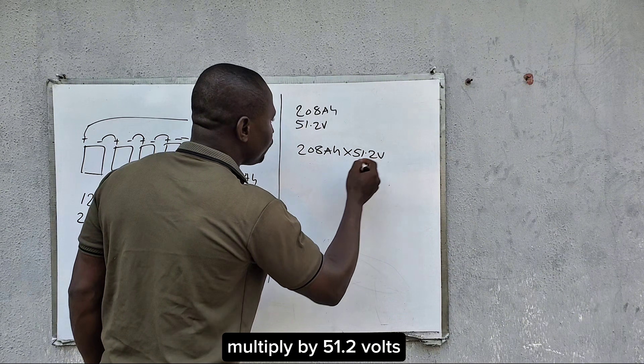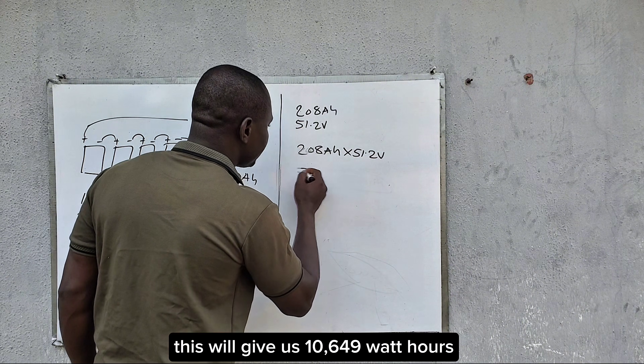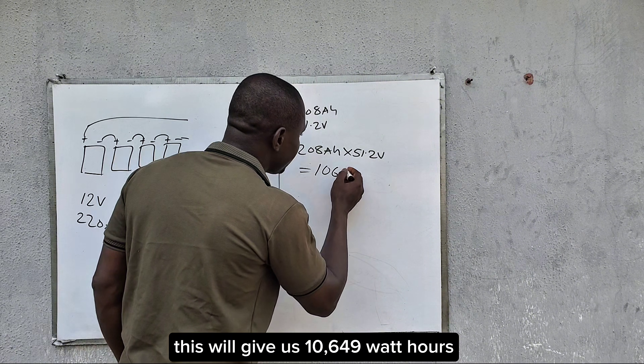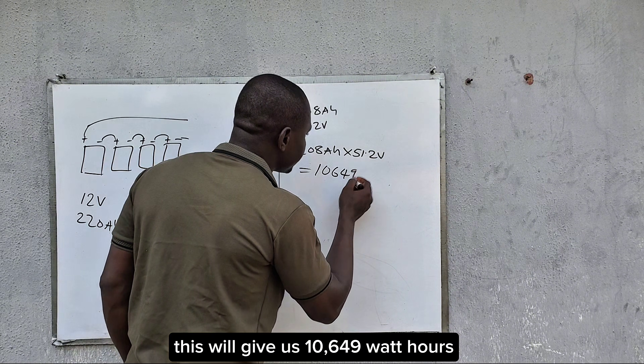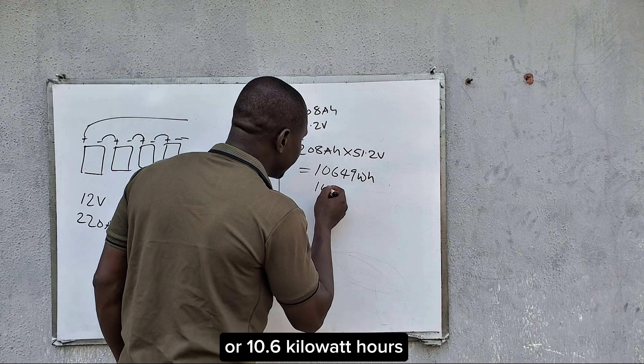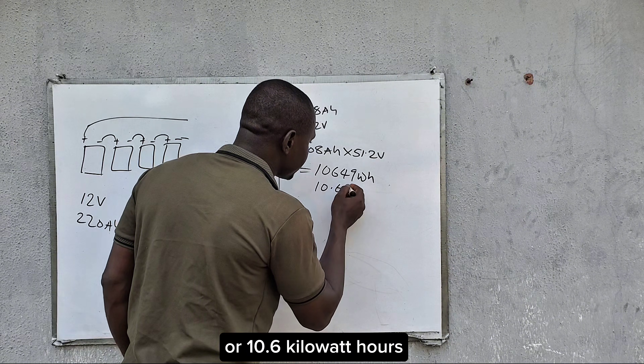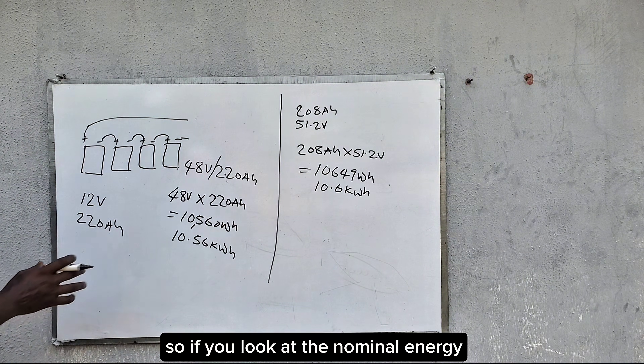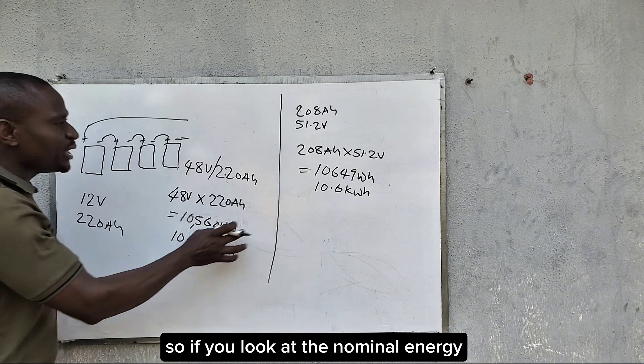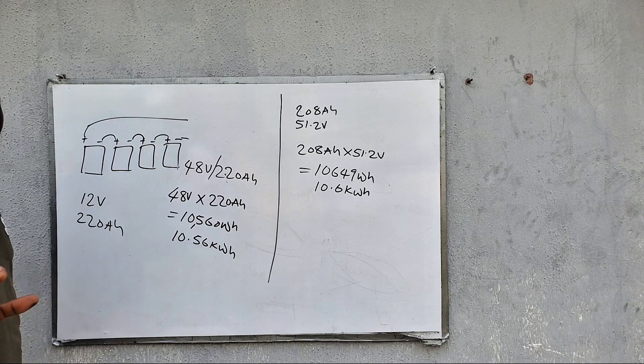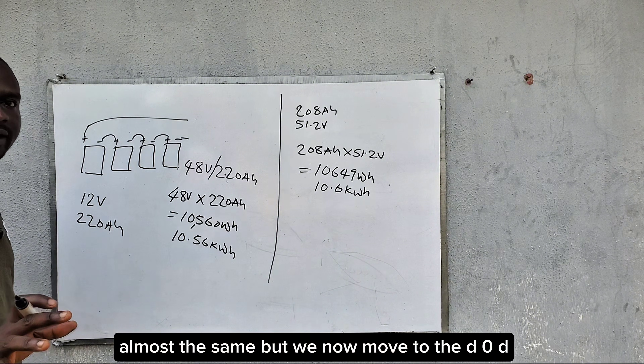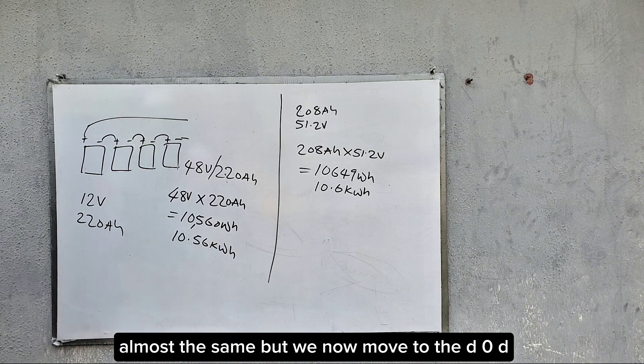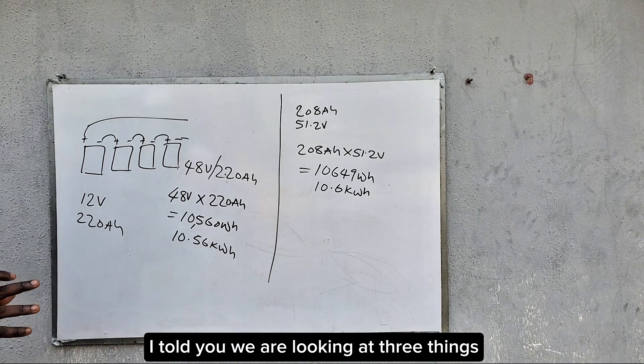For the lithium battery, the nominal energy is 208 amp hours multiplied by 51.2 volts, which gives us 10,649 watt hours or 10.6 kilowatt hours. So if you look at the nominal energy, it is almost the same. But now we move to the DoD.